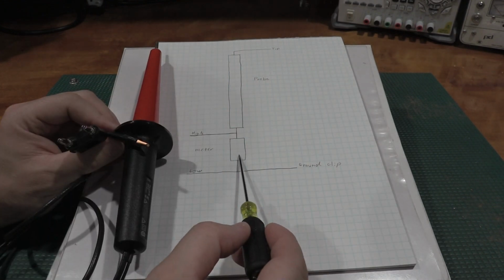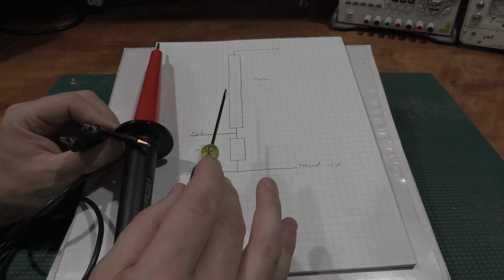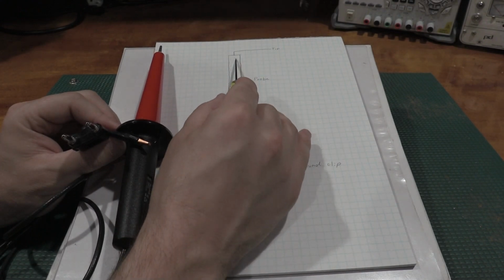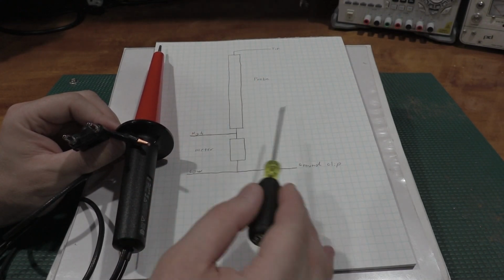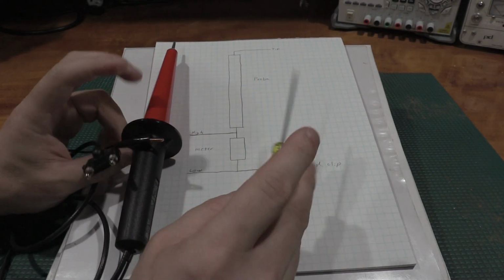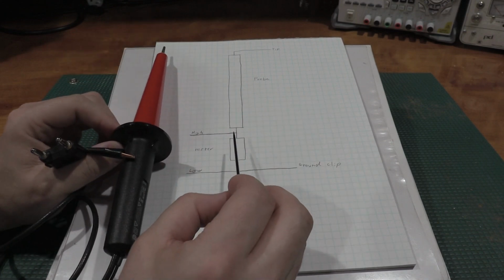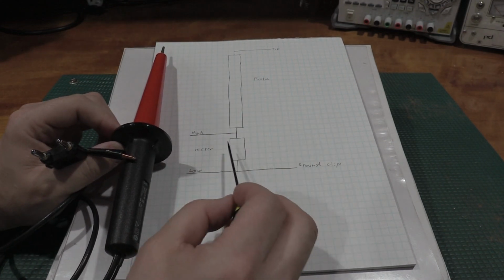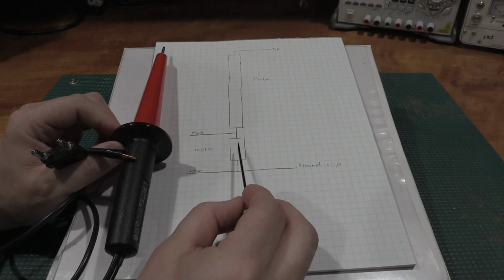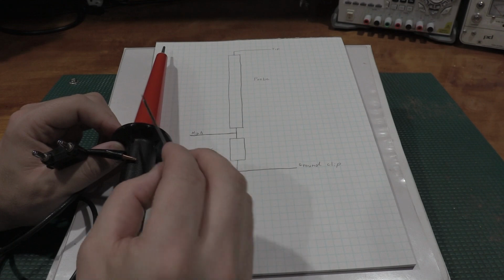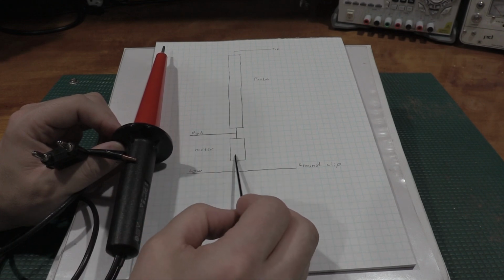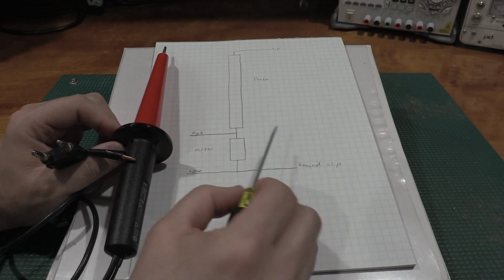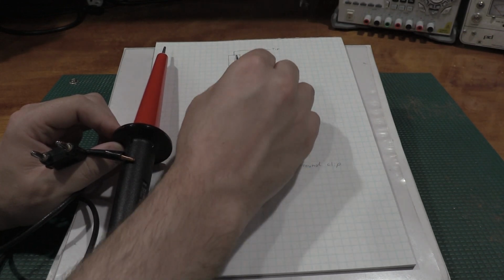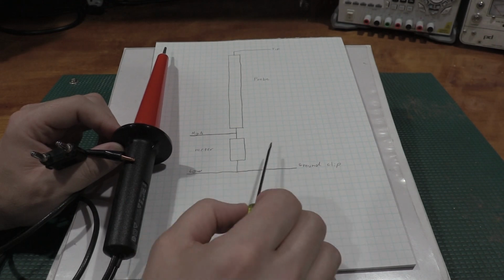So meter input impedances can move a little bit, a couple of percent. This is a fixed resistor. It will drift over time, but other than that, it, quote, doesn't move. So finding the meter that's in inventory that has the closest to 10 megohms gives you the best division ratio, because this will change with meters a little bit, and I'll show that here in a bit. This will not. So if this is off, it throws this division ratio out. The readings will be a little off.